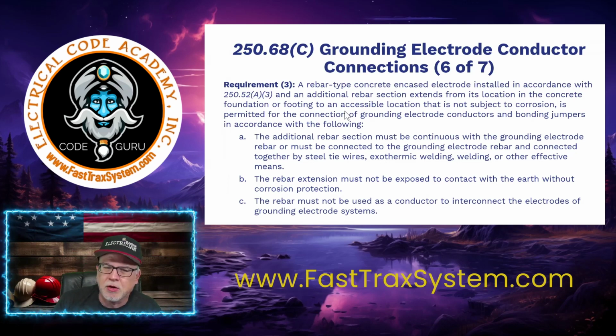All right, so let's look at a little more here. If we have the rebar and it qualifies, it says, and an additional rebar section extends from its location in the concrete foundation or footer to an accessible location that is not subject to corrosion. So it's not going to be outside. It's going to be in the interior of the building. It is permitted for the connection of grounding electrode conductors and bonding jumpers in accordance with the following. Don't worry, I've got an image. Our grounding and bonding course has some of the best images out there. I'm going to give you a visual in a second.